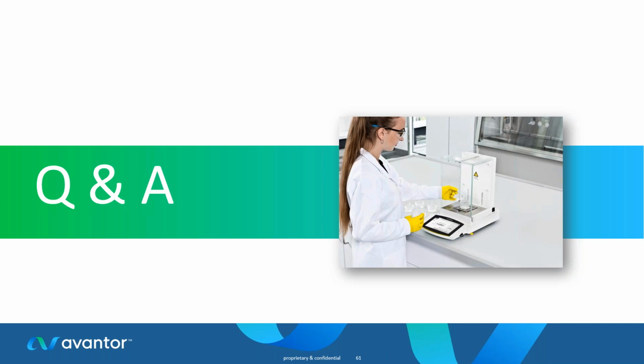Please share tips for cleaning of balances. This is an excellent question. We've just introduced on the high capacity microbalances in the Cubis 2 range a cleaning Q app. Now this is a small application which will remind you whether you need to do basic or advanced cleaning on your balance. It's integrated into user management, which is also recorded in the audit trail. So you can check whether somebody has agreed that they've cleaned the balance, either a basic or an advanced clean.